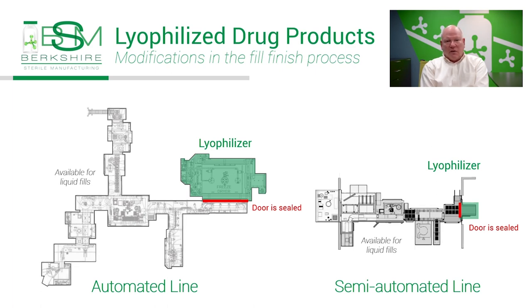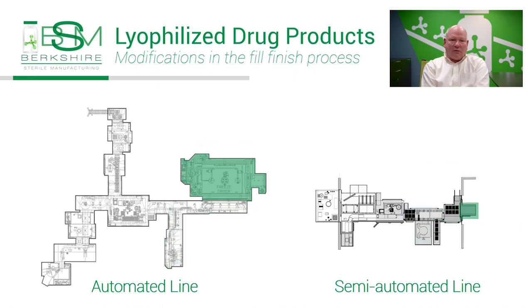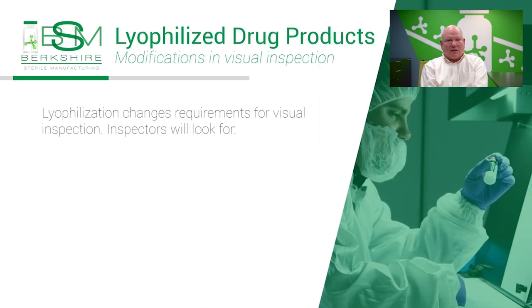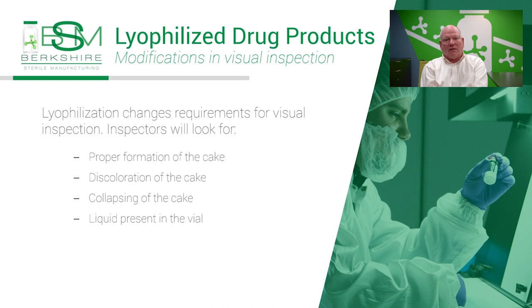These lyophilizers are sealed off while the cycle is running, which allows us to VHP the other chambers in the filling line and perform liquid fills of other products while the lyo cycle is occurring. This reduces the amount of time that our filling line is out of commission. Once the cycle is complete, we sanitize the chambers with vapor hydrogen peroxide, unload the product in the isolator, and transport the vials to the capper. Lyophilization helps protect the drug products, and inspectors look for proper formation of the cake, discoloration, collapsing, and ensure there is no liquid present in the vial.